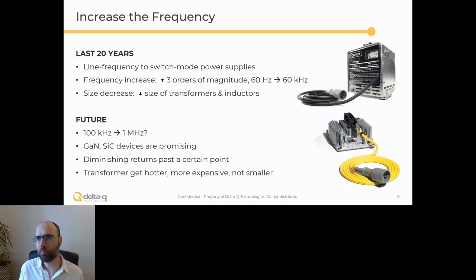There's not a Moore's law for power electronics the way there is for processing power. The reason is that processing power can get arbitrarily small until you hit the atomic scale, because you're not actually doing any work—you're just moving ones and zeros. But here, we're actually processing watts, represented by physical currents and voltages, and there are real losses tied to that. So past a certain point, your transformer stops getting smaller, and it mainly starts to get hotter and more expensive.